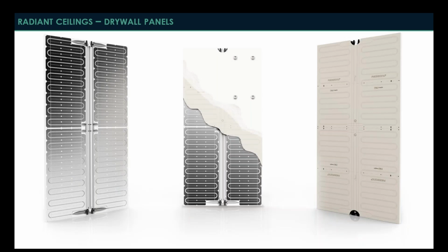Another type of radiant ceiling panel is a drywall panel. So sometimes you have drywall ceilings, whether that is in a conference room, an elevator lobby, just areas that don't want to have an acoustic ceiling tile ceiling. But if you're utilizing a radiant system, you need something that works well in that type of environment. And these drywall radiant ceiling panels can do exactly that. And they come prefabricated from the manufacturer, essentially with all of the radiant tubing already installed and with drywall finished on the face of that panel at the factory.